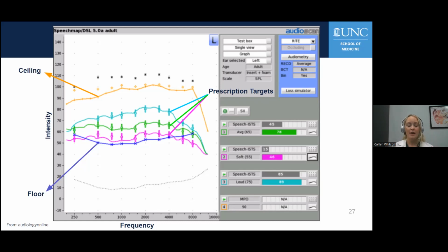But we know because of resonant characteristics. If you have a really big cavity versus a really small cavity, it affects what sound waves travel through, are amplified or attenuated. So the size and shape of someone's ear canal can affect what sound leaves the hearing aid and actually reaches the eardrum. The estimations by the computer software are just that. They're estimates based on an average sized ear canal. I have never run this measurement on anyone and had it match perfectly with the manufacturer's software estimate of where it should be. It is almost always too soft.